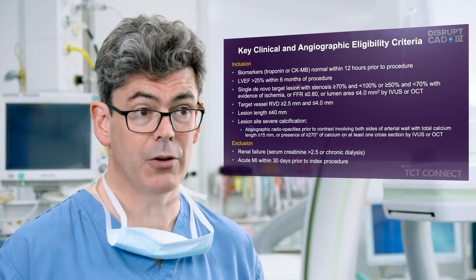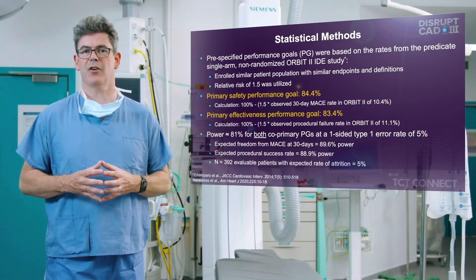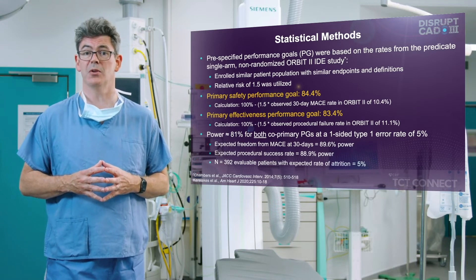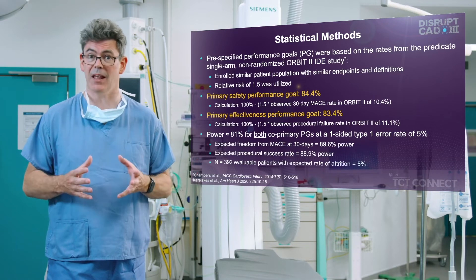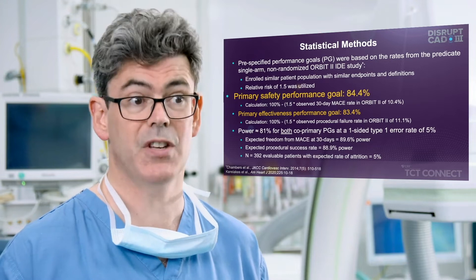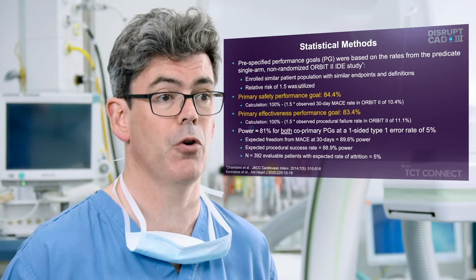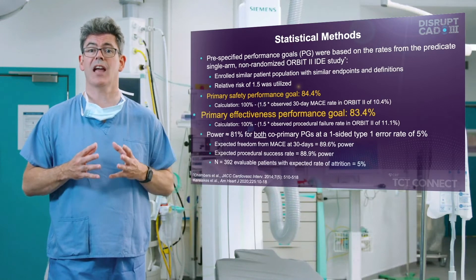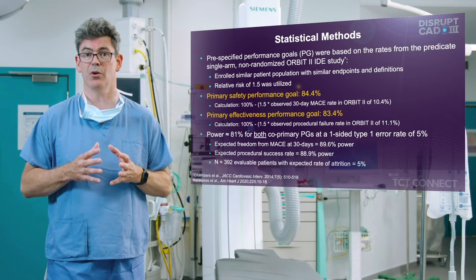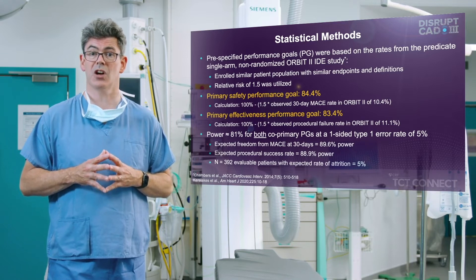Exclusion criteria included renal failure defined as creatinine greater than 2.5 or dialysis, and myocardial infarction within 30 days. The pre-specified performance goals were based on rates from the predicate single-arm, non-randomized ORBIT2 IDE study for orbital atherectomy, which enrolled a similar patient population with similar endpoints. A relative risk of 1.5 was used per FDA guidance. The primary safety performance goal was 100% minus 1.5 times the observed 30-day MACE rate of 10.4%, and the primary effectiveness goal was based on the procedural failure rate in ORBIT2 of 11.1%. The study was over 80% powered for both co-primary performance goals at a one-sided type 1 error rate of 5%.